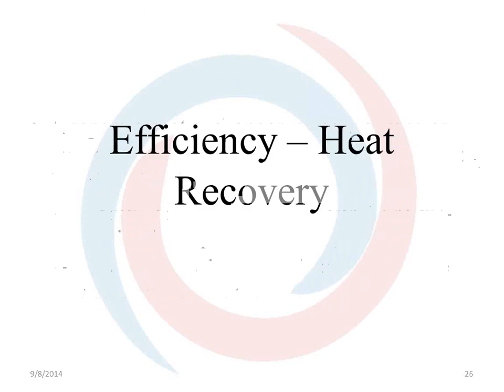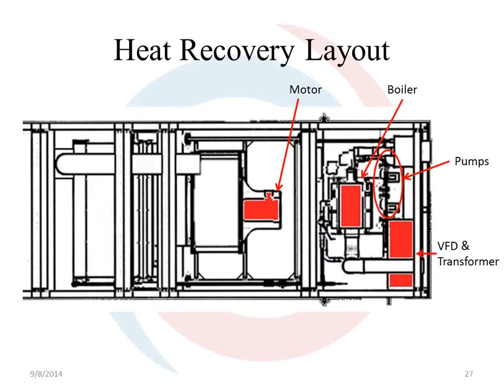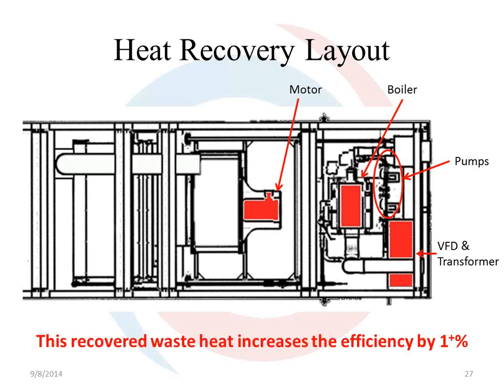Let's talk a little bit about the energy recovery. This is the boiler compartment here with the VFDs, the pumps, everything else. This is open to atmospheric pressure. Here, of course, is the fan motor. Heat recovery recovers the heat from all these heat generating devices here just by using natural progression from the higher pressure areas down to the lower pressure areas. Of course, there's a negative pressure in front of the coil. So the air just translates right down here and it gets reclaimed, all that heat from the pump, the VFDs, the boiler, and that recovered waste heat increases the efficiency by 1%.